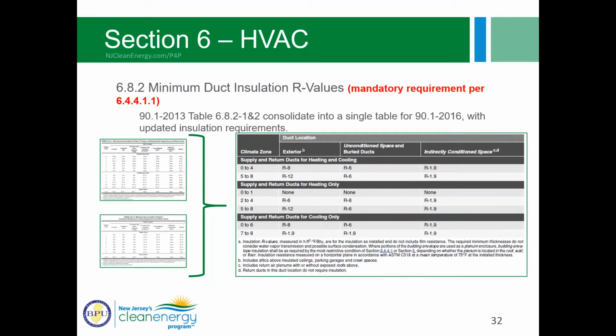All right. With HVAC, this is our last slide for air conditioning, and then we're going to be heading into service water heating. This is going to be a mandatory requirement because table 6.8.2 is referenced from within section 6.4.4.1.1. So for example, just looking at climate zone 4, if we had an exterior duct with heating only, this would be our attics above insulated ceilings, parking garages and crawl spaces. The requirement was R3.25, now it's R6.